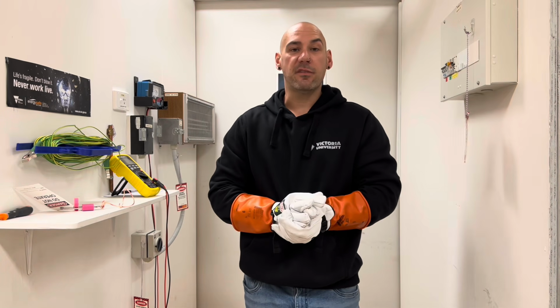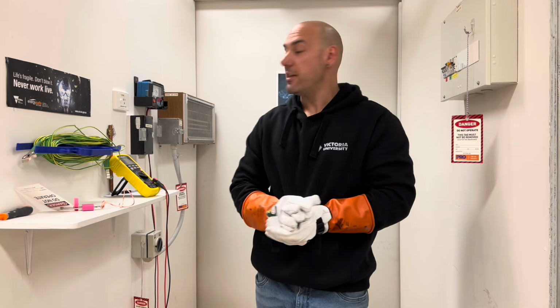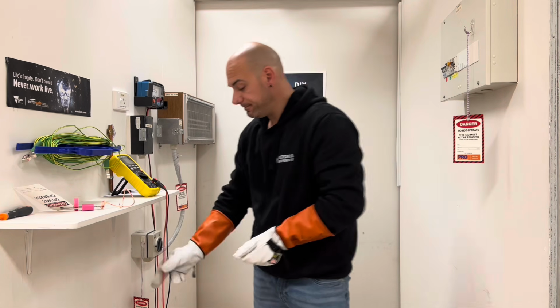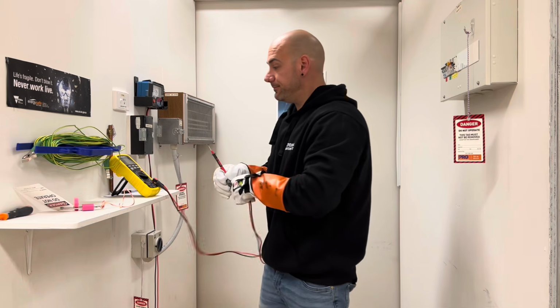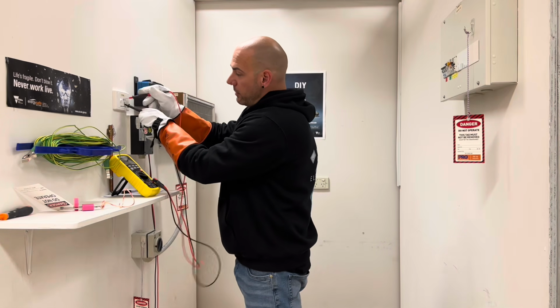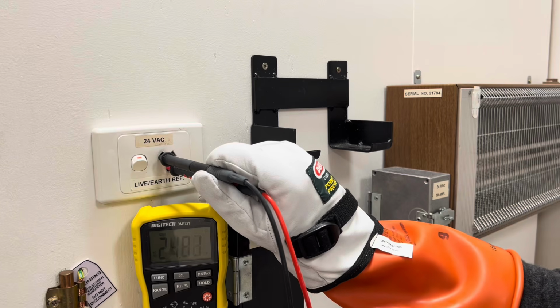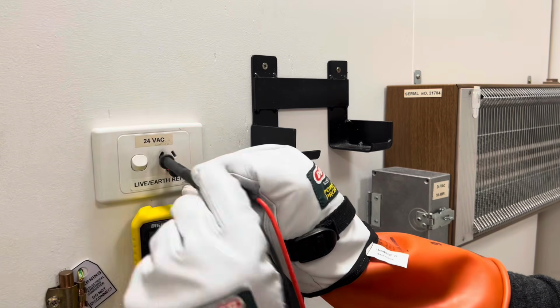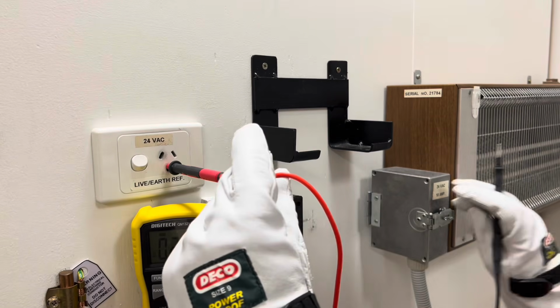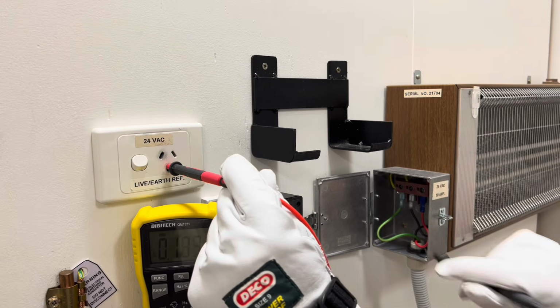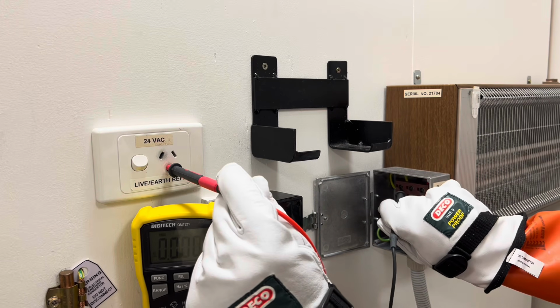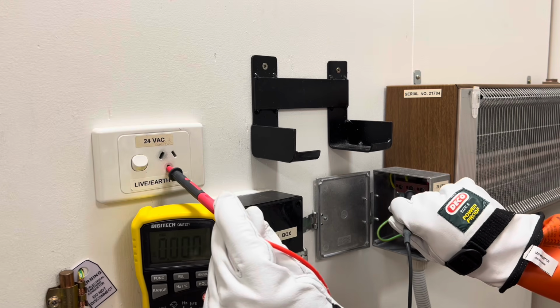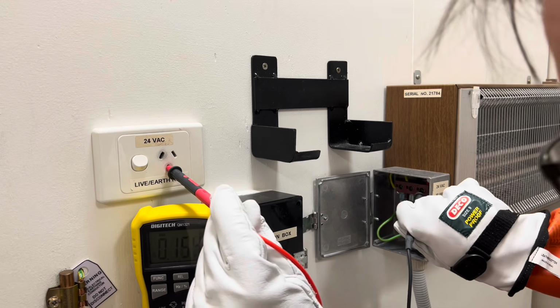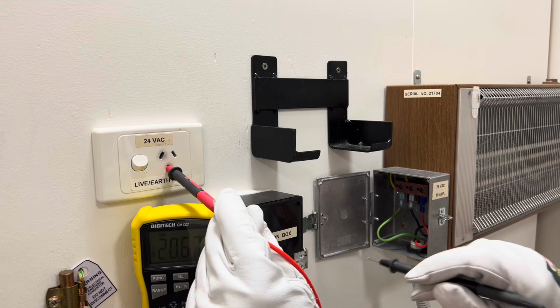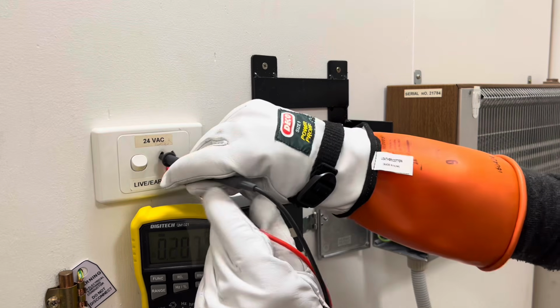Now we conduct a voltage test to see if there is voltage at the terminals of the heater. Get our voltmeter. We test it on our reference voltage. Voltage there. From our reference earth, that is 0 volts. Earth to neutral, 0 volts. Earth to active, 24 volts. We test our meter. Okay.